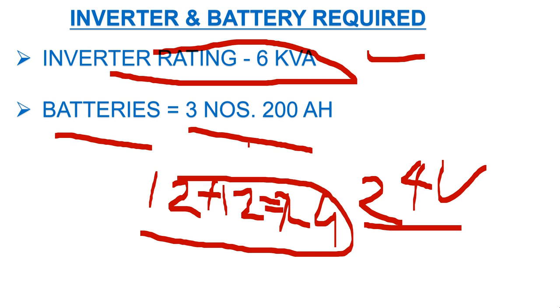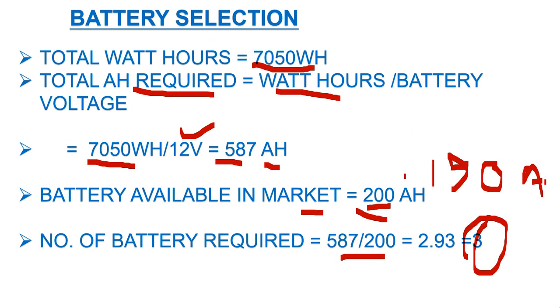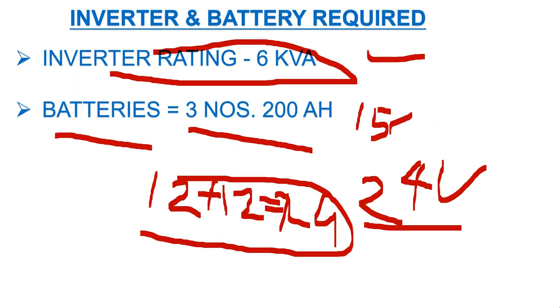In conclusion: for this load you need a 6 kVA inverter. Note that for inverters above 3 kVA, the operating voltage is 24V, so batteries must be connected in series — 12V + 12V = 24V. Based on our calculation you need either 4 batteries of 150 Ah or 3 batteries of 200 Ah. I hope you understand how to calculate and select the inverter and battery. Please subscribe to the channel and share this video — thank you.